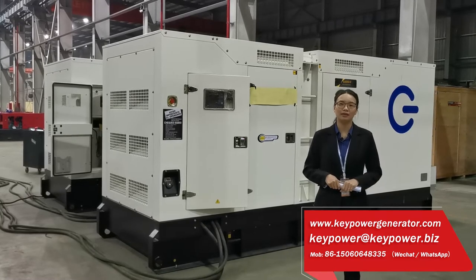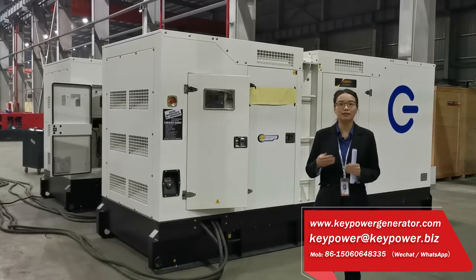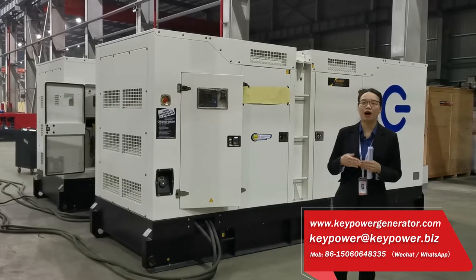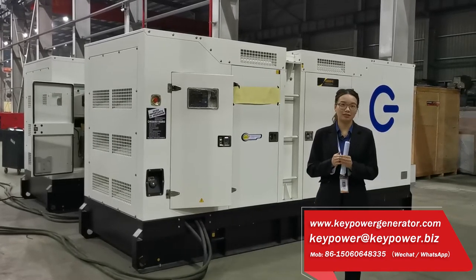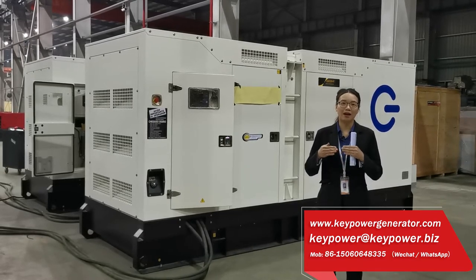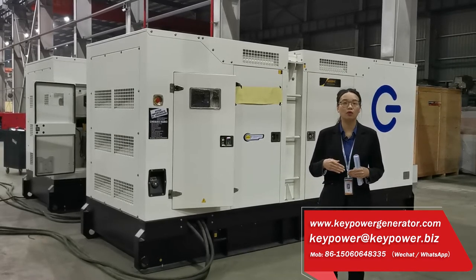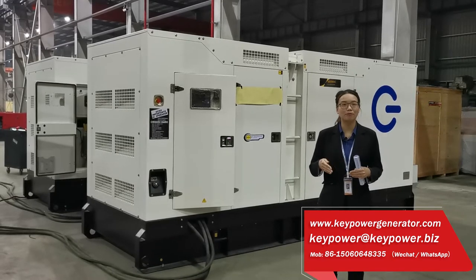At this point, some friends will ask me, if the generators have different power, whether they also can work in parallel? Yes, for generators of different power, as long as they have the synchronization function, they will work in parallel. They will not share the load half and half. They will share the load at the same rate.